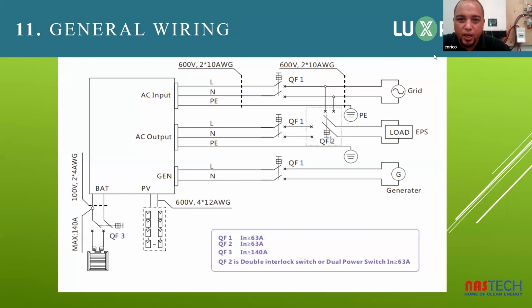The general wiring inside the inverter. These are our relays for remote control. These are our remote control relays. This is the battery switch, the main isolator for the batteries. This is your solar panels, up to 480 volts. This is just your general overview of the relay switches within the inverter that are programmable through the web page in terms of normally open or normally closed. So these relays can be set according to the max output, or also the time slots in which you want to use the grid, or the time slots in which you allow the battery to charge and discharge.